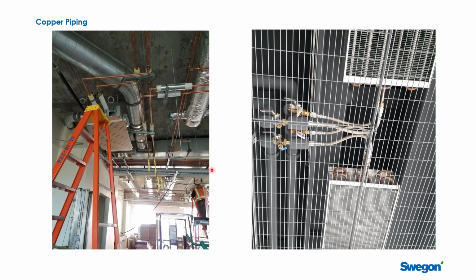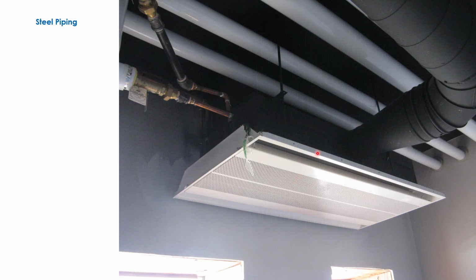It's a nice touch. This is actually a passive chilled beam application here. So you've got piping coming in here, and where you can add water to these things. And again, you can see the flexible hoses and the ball valves to isolate it. Here is a different application. This is an exposed beam, but notice that they're actually running steel or black iron pipe here, and then hard connecting in here. This is less common, but certainly possible to do.